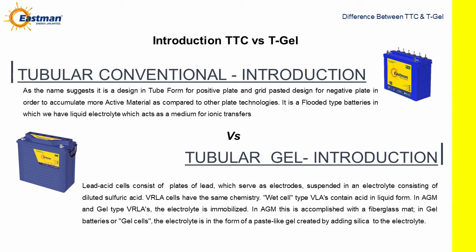Tubular Gel. Lead acid cells consist of plates of lead, which serve as electrodes, suspended in an electrolyte consisting of diluted sulfuric acid. VRLA cells have the same chemistry. Wet cell type VLAs contain acid in liquid form. In AGM and gel type VRLAs, the electrolyte is immobilized. In an AGM, this is accomplished with a fiberglass mat. In gel batteries or gel cells, the electrolyte is in the form of a paste-like gel created by adding silica to the electrolyte.